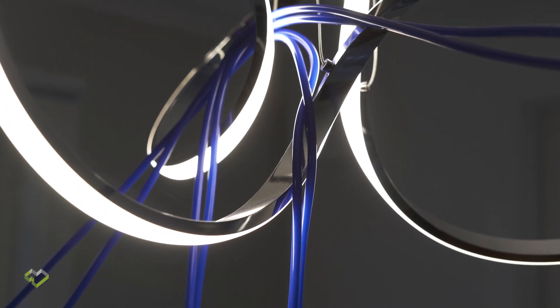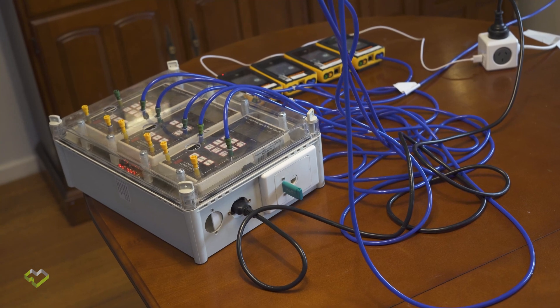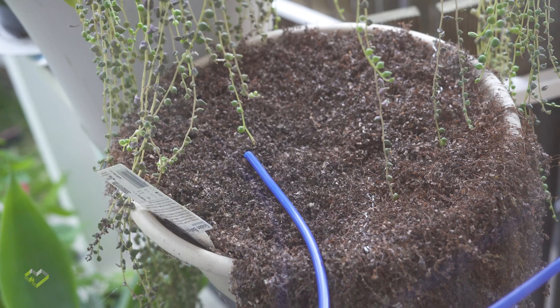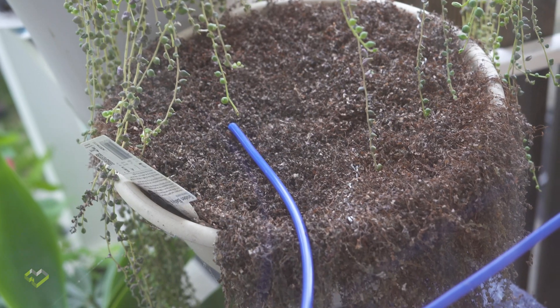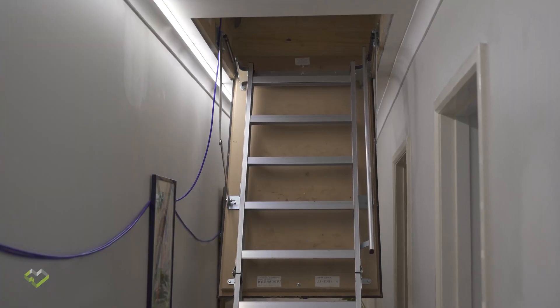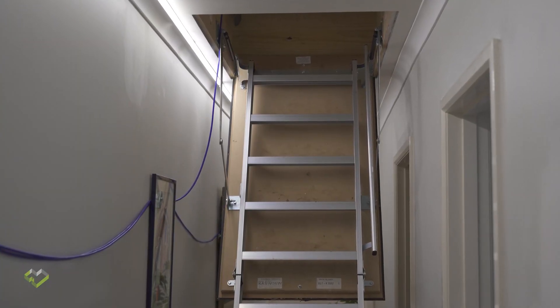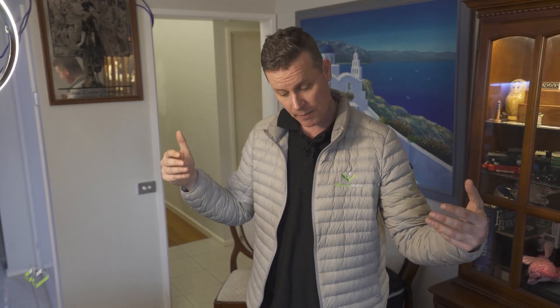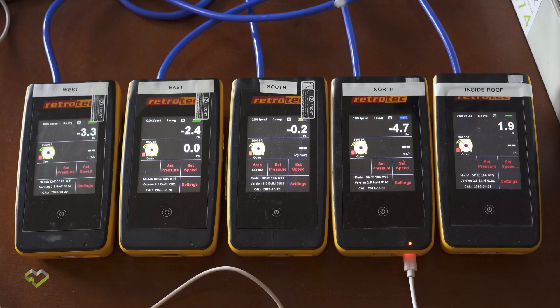What we've shown here is we're capturing the pressure differentials on all four — five sides of this home. We're showing how some parts of the building envelope go into positive pressure and some other parts go into negative. This combination of pressures at the same time is where a lot of our conditioned air can go straight to the outside.